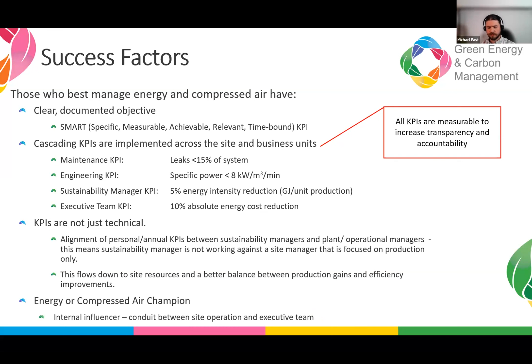So I want to pull that together to give an example of what a compressed air strategy might look like. This is one I'm working on at the moment. The system isn't the biggest, but it's reasonable with a 30 kilowatt compressor, and it was observed to be approaching maximum capacity, with times in the day where it was running flat stick for 8 to 10 minutes.